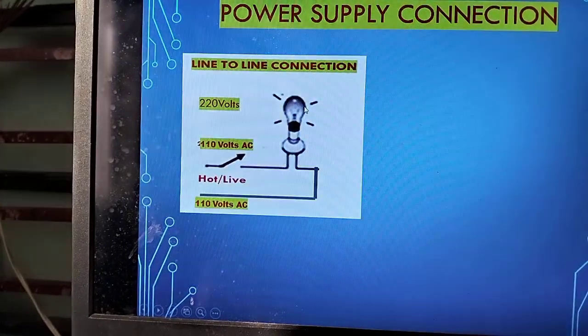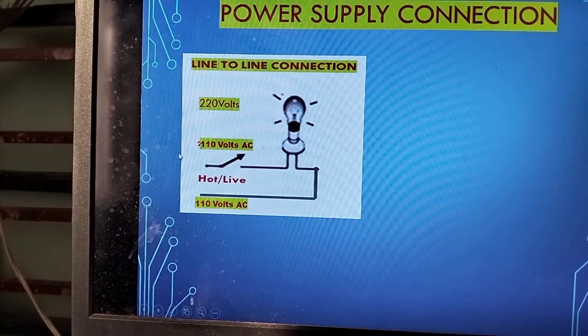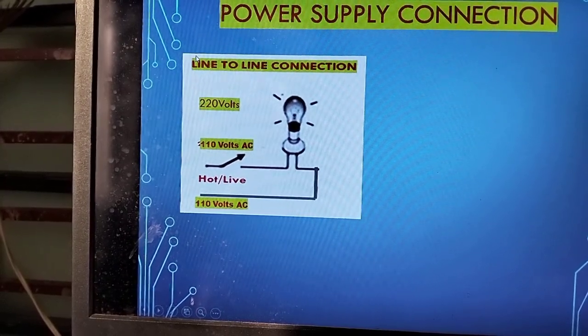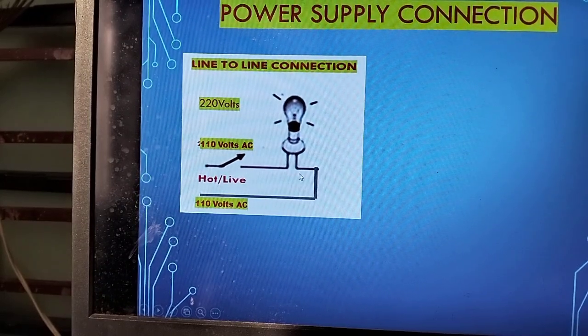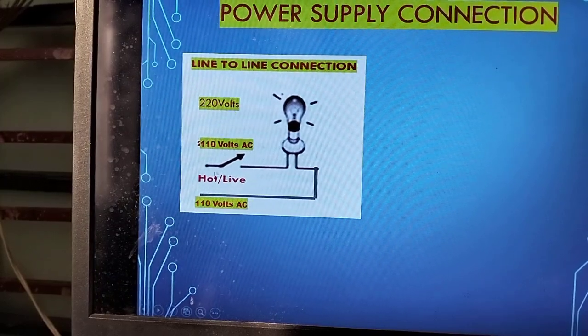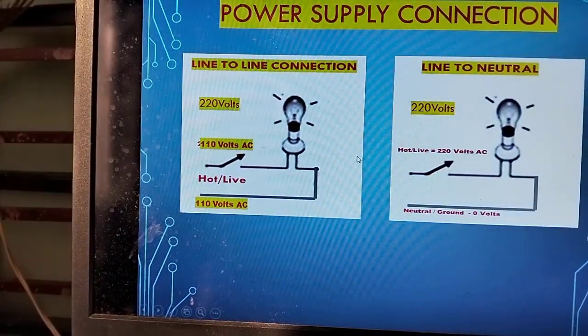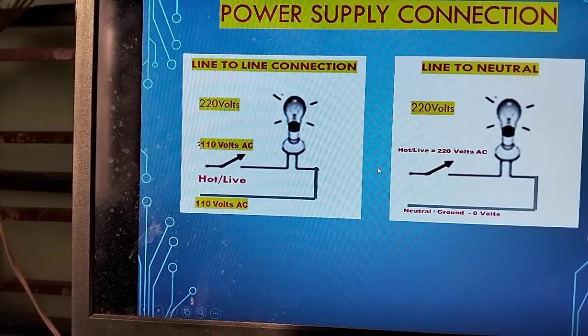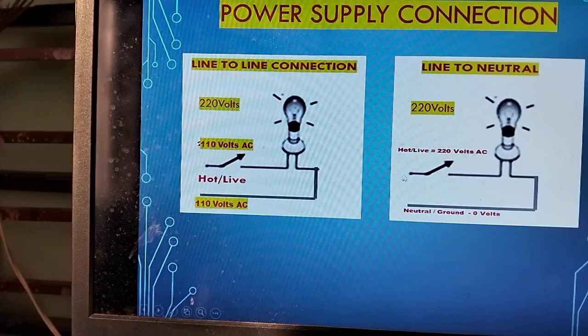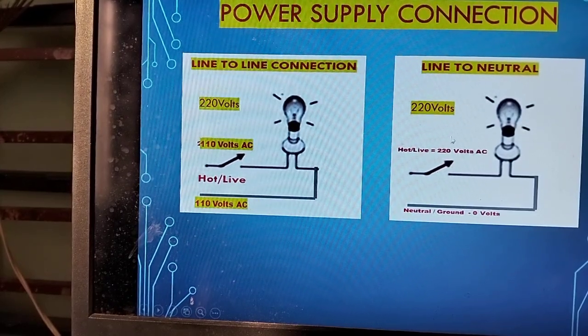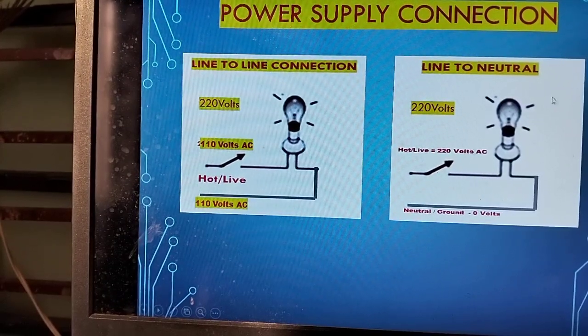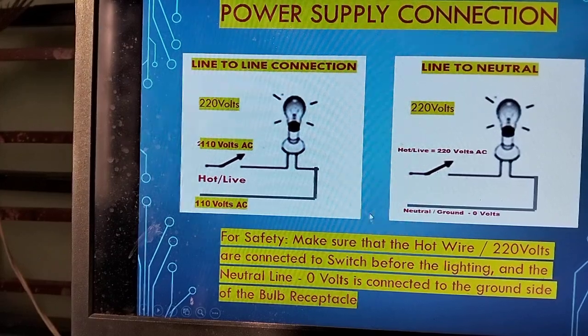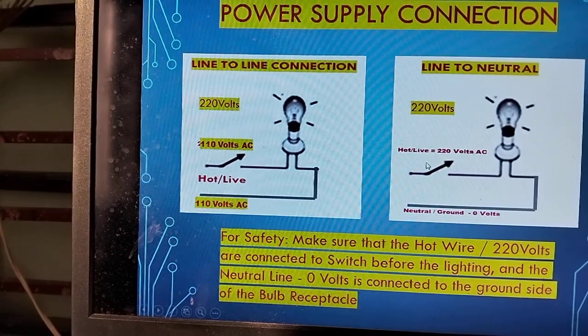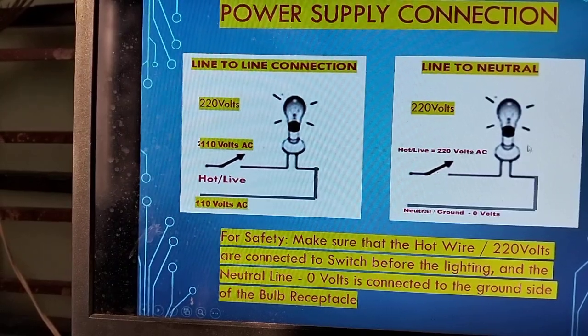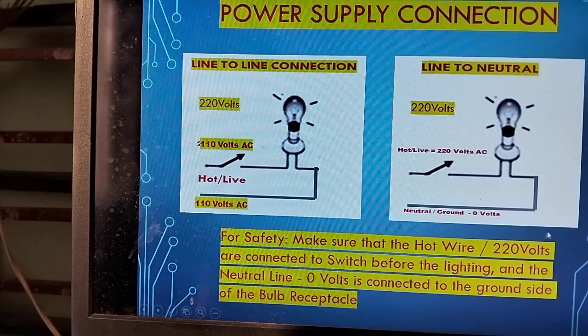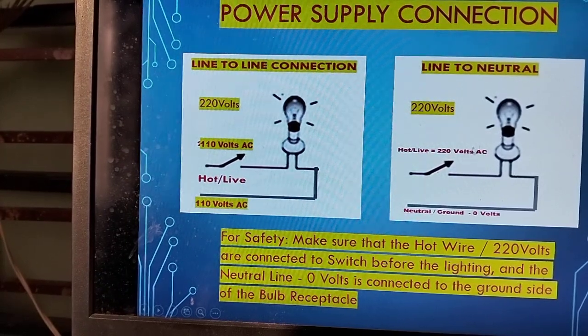Some of this, like this line-to-line connection here in the Philippines. In particular, in my place, we are using line-to-line. One line is 110, another line is 110, so it has 220. In the other town, they are using line to neutral. One line is the hot wire or live wire, 220 volts, and the other one is neutral, 0 volts. For safety reasons, make sure that the hot wire is connected to the switch before the lighting, and the neutral line, 0 volts, is connected to the ground side of the bulb or receptacle.